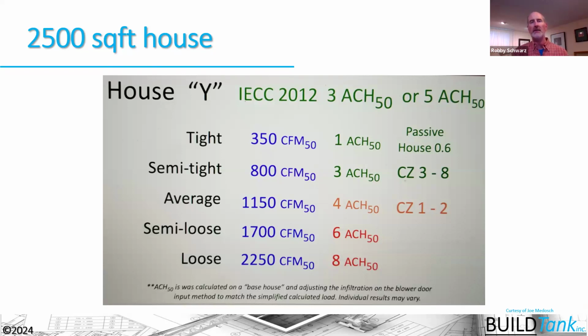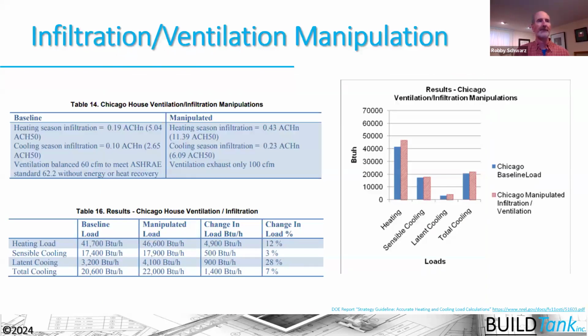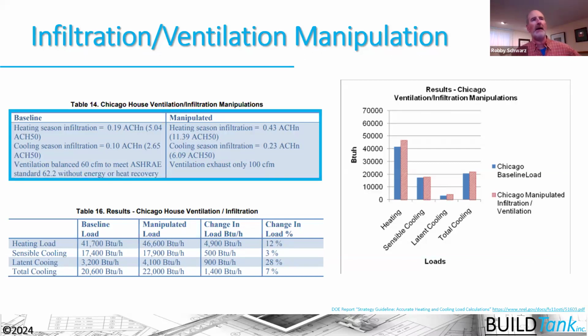And we're continuing to get our houses tighter and tighter and gain more control and predictability. So if you were using average loose or semi-loose in the calculation, frankly, you're going to be manipulating the software and oversizing the equipment that's installed here. So with regards to infiltration and ventilation, that study that the IBACOS group was doing, we see that they manipulated the ventilation rates in these houses, and we're getting load changes from 12% in the heating season and 7% in the cooling season. So you can see this is impacting the heating season loads more than the cooling season, whereas the other manipulations were really manipulating the cooling season loads more than the heating season loads.